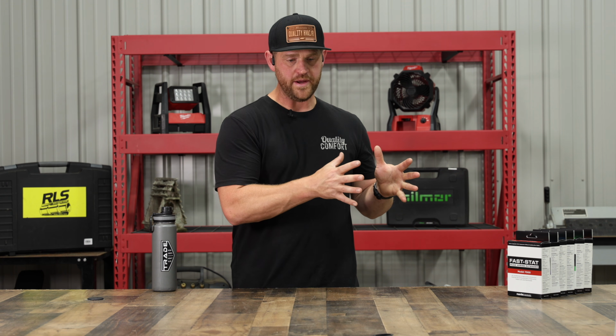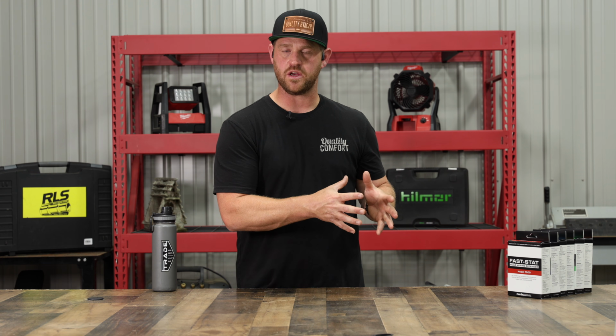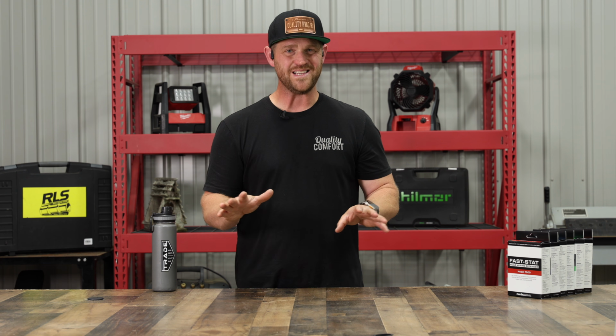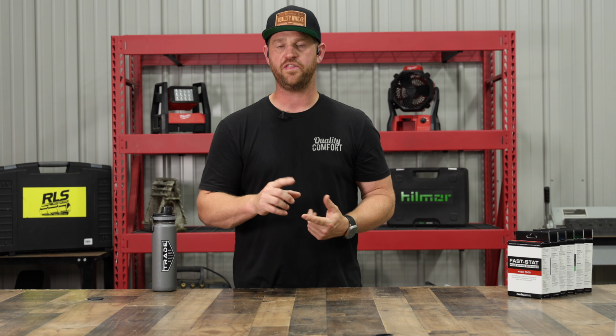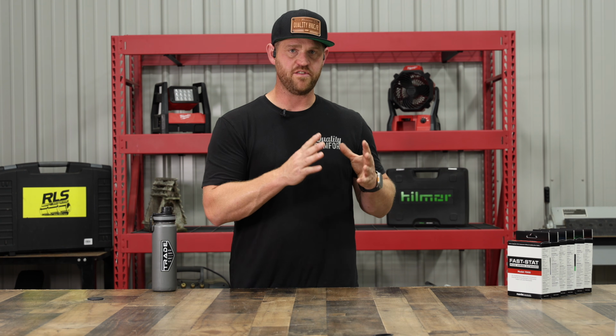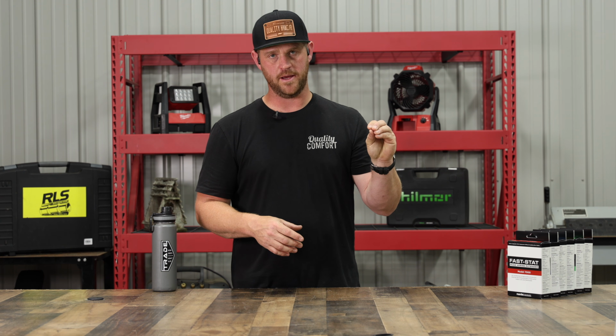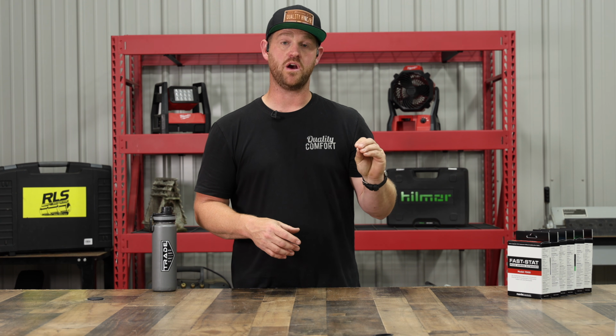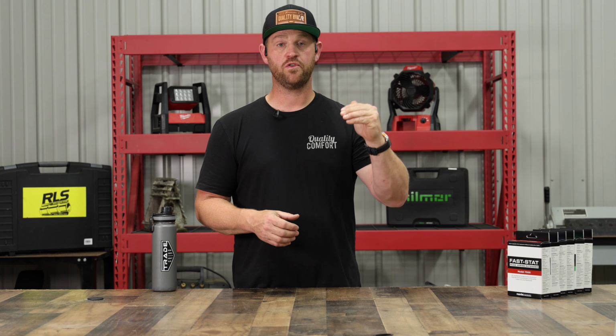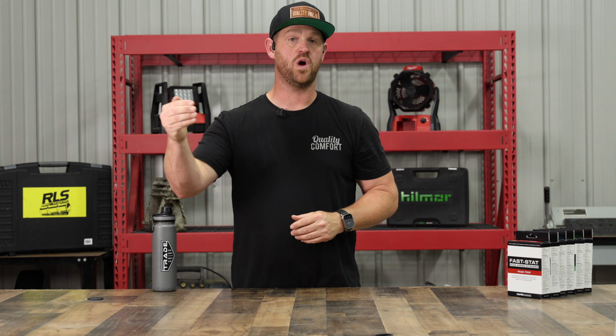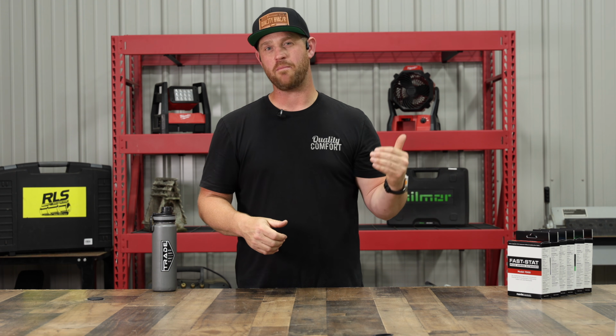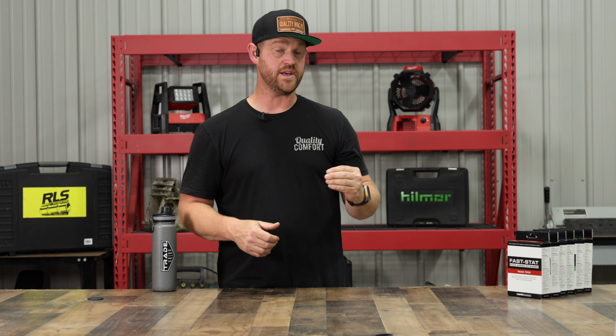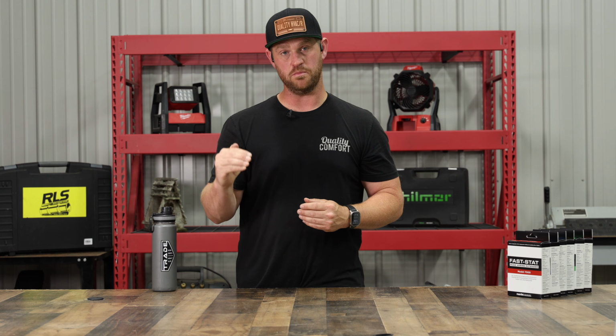Now, going to high efficient equipment alone is not going to control humidity. That's one thing we need to talk about. Now, if you have a thermostat that shows your humidity, it might have the opportunity to overrun the system. What I mean by that is it might let it continue to run and let the temperature drop maybe 1 degree or maybe even 2 degrees because we're trying to knock down that humidity.